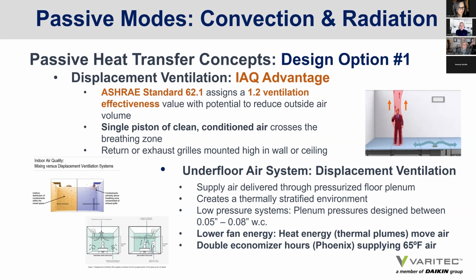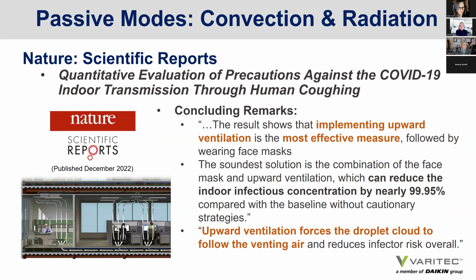There's another energy efficiency advantage to underfloor displacement ventilation. So, is underfloor effective in creating healthier environments? Well, according to a Nature Scientific Reports publication in 2022, implementing upward ventilation is the most effective measure, followed by wearing masks, to reduce the risk of infection. In fact, it says that it can reduce the indoor infectious concentration by nearly 99.95%, compared to a mixed air system, which is doing its job if contaminants in that space are being well mixed. And there are some arguments in the market today that are challenging our concept of how contaminants actually travel back to an air handler. Do the smaller submicron particles actually make it back to the air handler to be properly filtered?